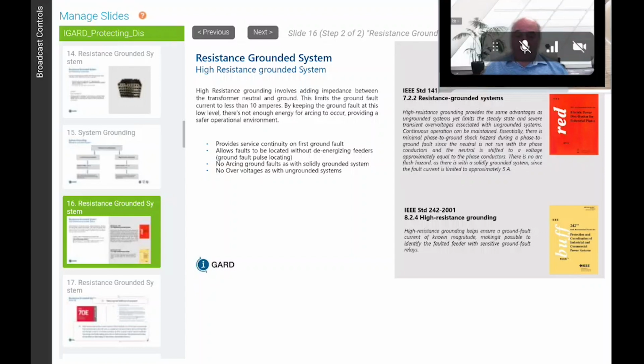So the Buff book says resistance grounding helps ensure ground current of a known magnitude, making it possible to identify the faulted feeder and isolate it. Or more importantly, we can locate where the fault is in that high resistance grounding system without shutting anything off and without opening any doors, exposing your personnel to hazardous voltages. We've gone out and looked for ground faults in facilities, and I can guarantee that I can locate a fault in any size facility in less than an hour with a high resistance grounding system, without shutting down and without opening any doors.